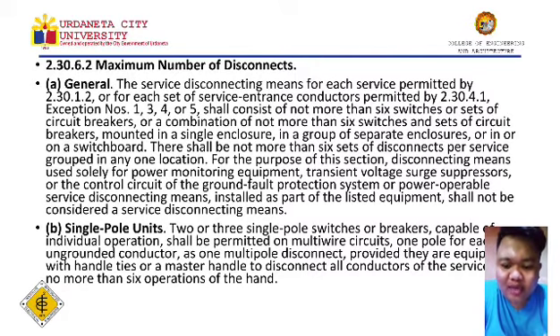2.30.6.2 Maximum number of disconnects. A. General. The service disconnecting means for each service permitted by 2.30.1.2, or each set of service entrance conductors permitted by 2.30.4.1 Exception numbers 1, 3, 4, or 5, shall consist of not more than 6 switches or sets of circuit breakers, or a combination of not more than 6 switches and sets of circuit breakers, mounted in a single enclosure, in a group of separate enclosures, or in or on a switchboard. There shall be not more than 6 sets of disconnects per service group in one location.